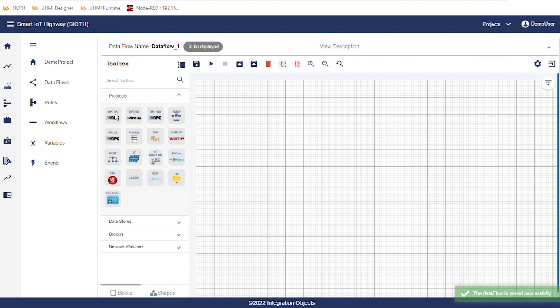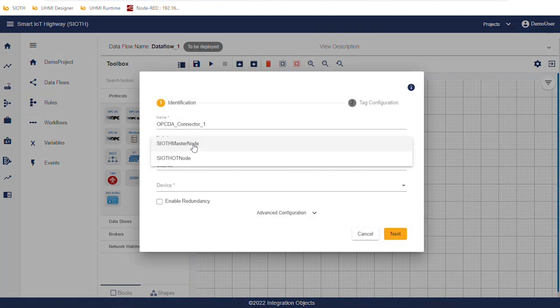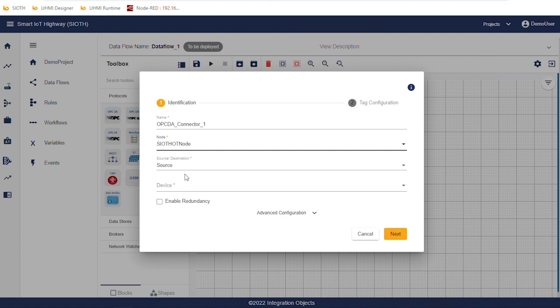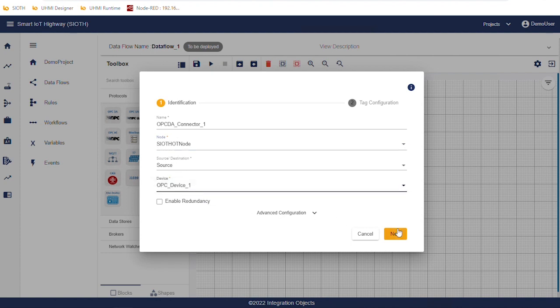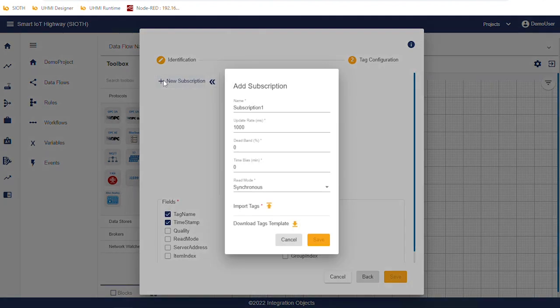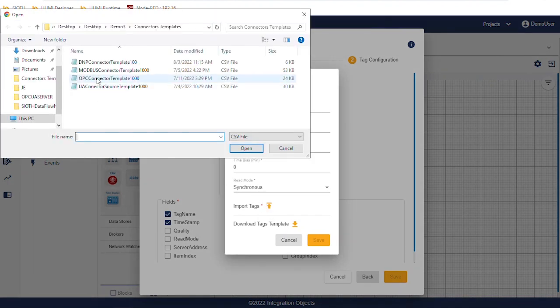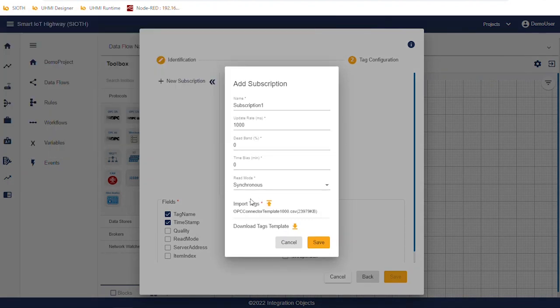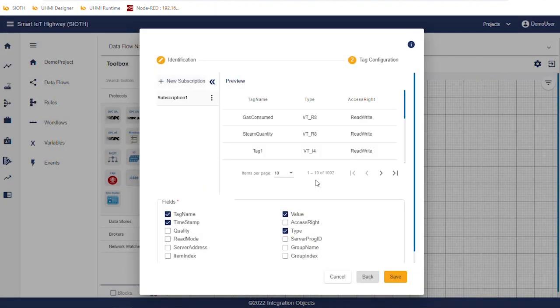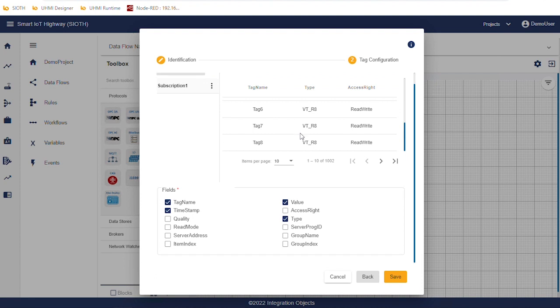From the toolbox, drag the OPCDA block and drop it in the workspace. Click the settings icon. Select the node where the connector will be hosted. Select the OPCDA device. Then, click on next. Click on add subscription. We can keep the update rate to one second and then click on import tags to specify the tags that we will read from the OPCDA server. Here is the list of OPCDA tags added automatically using the CSV template.